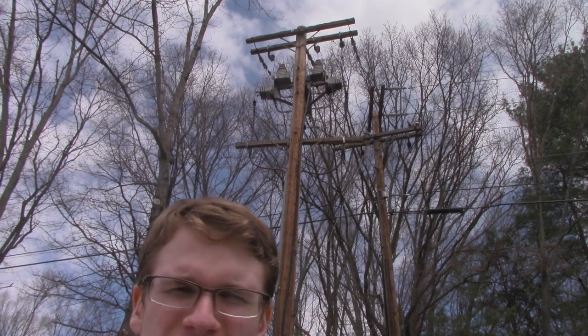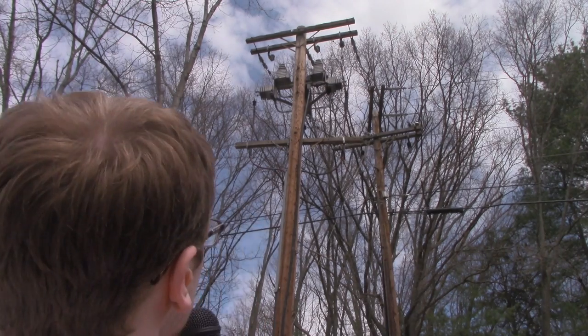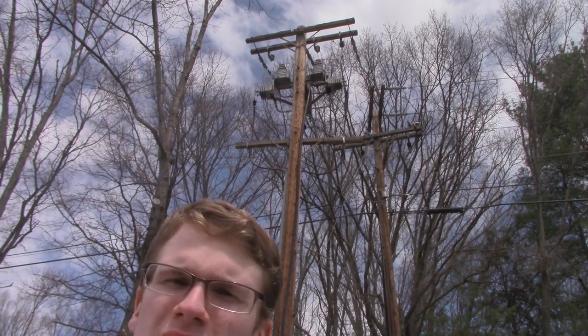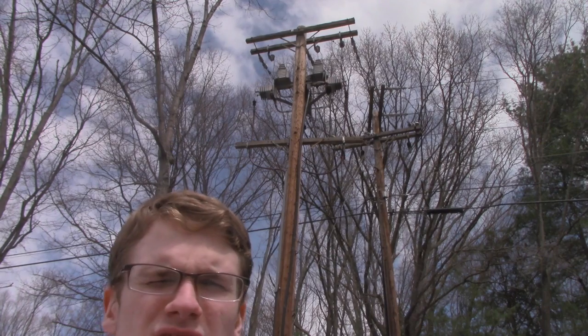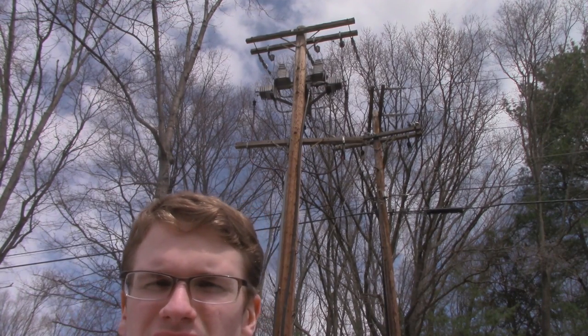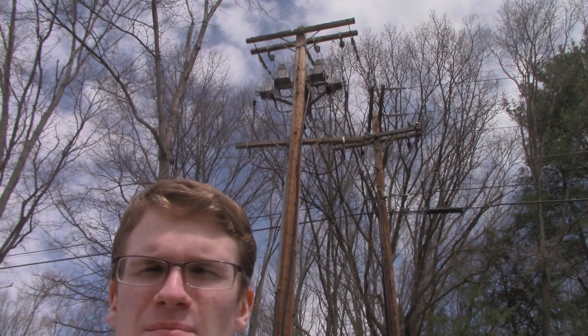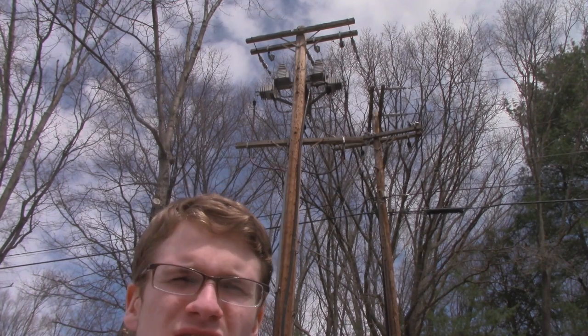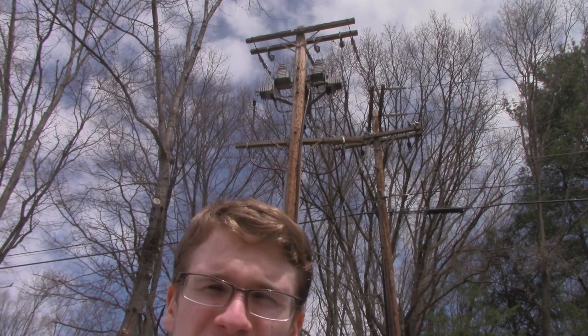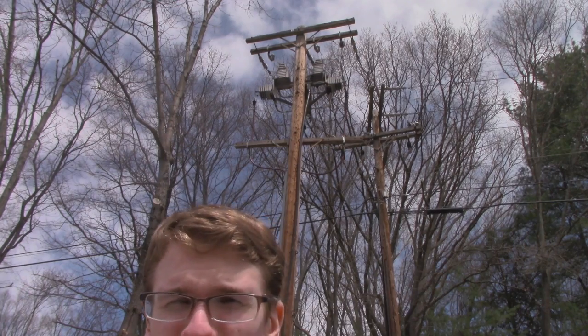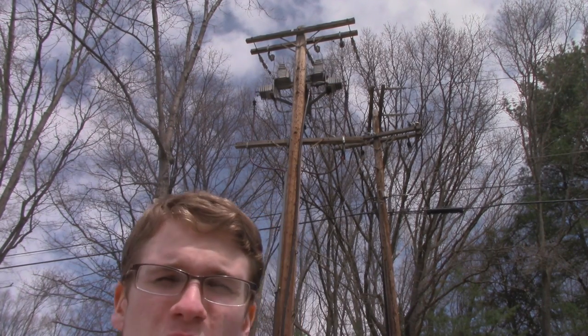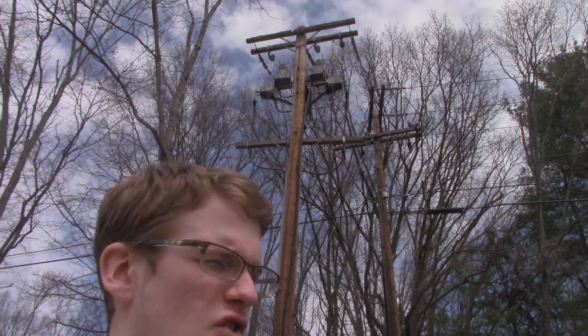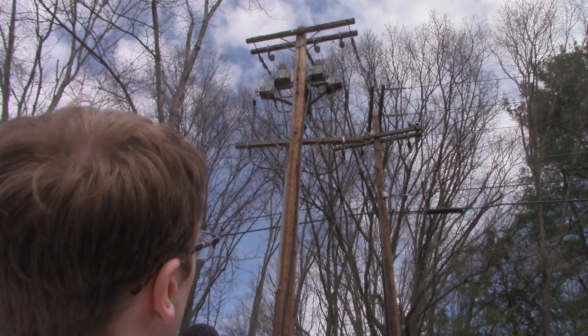Right up here, some important pieces of hardware for the grid would be on that pole further back. At the top, there are things called cutouts, essentially fuses so that if there's an overload on the line, they cut out and stop the flow of electricity to prevent damage. Often, if you hear a bang and then the power goes out, people think it's a transformer, but that's often wrong. It's usually a cutout because they make quite a loud sound. There may also be a form of power factor correction right up at the top of that pole.